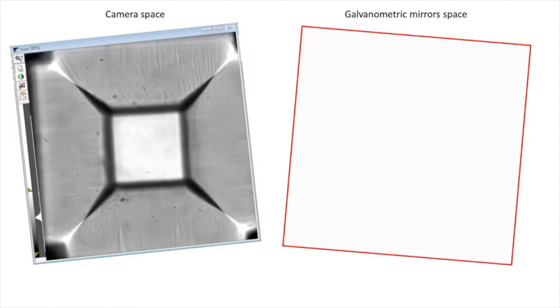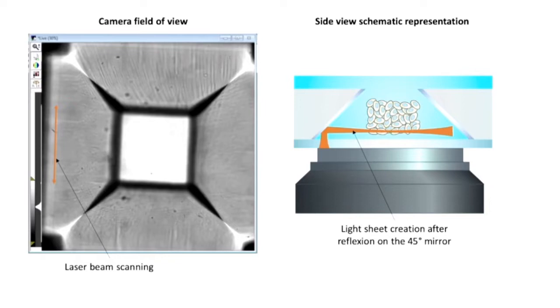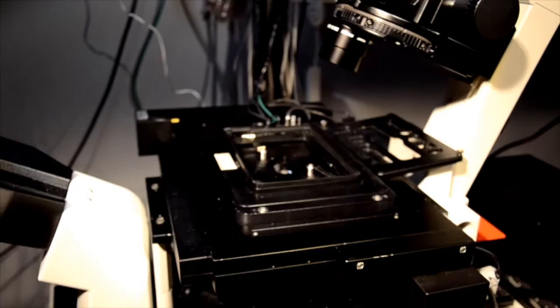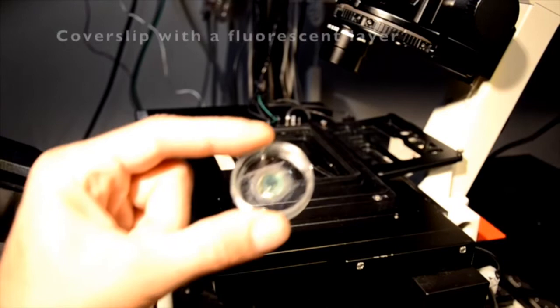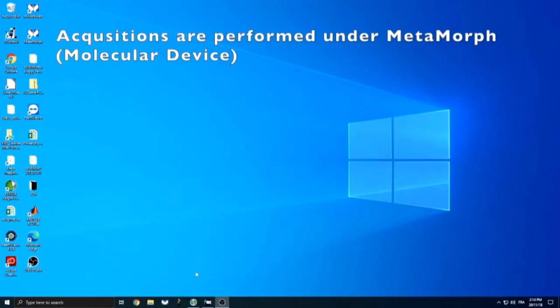A first calibration has to be done in order to superpose the galvanometric mirror space onto the camera space. This is mandatory to accurately control the laser beam position in the image plane and thus onto the 45-degree mirror to create our light sheets. This calibration is stable for months and only needs to be repeated when hardware such as the camera, the objective, or the filter cube has been moved. For this calibration step, we use a coverslip with a fluorescent layer on it, simply made with a fluorescent marker located on our stage holder.